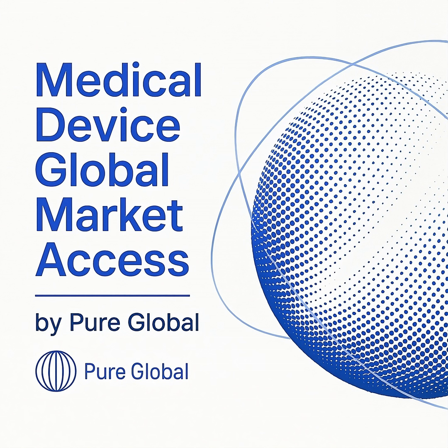In this episode, we are diving into a cornerstone standard for our industry, ISO 14971, focusing on the 2019 revision, which is the third and current edition for the application of risk management to medical devices. This standard provides a comprehensive framework for manufacturers to identify, assess, control, and monitor risks throughout a device's entire lifecycle, from initial concept to post-market activities.